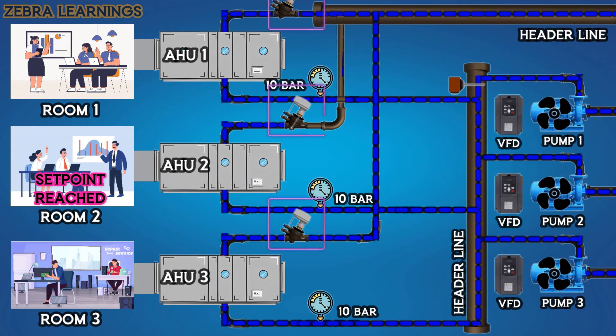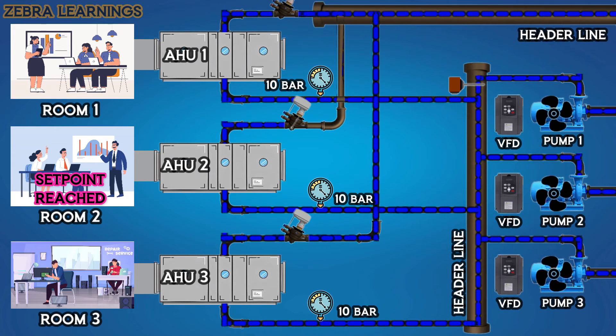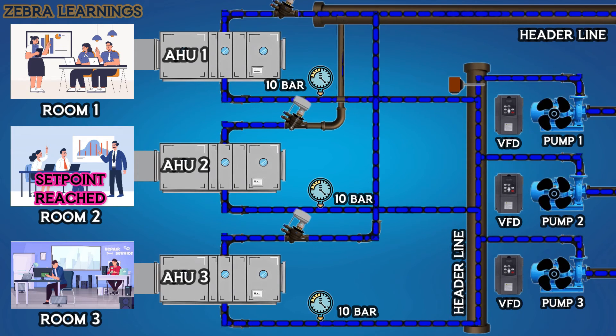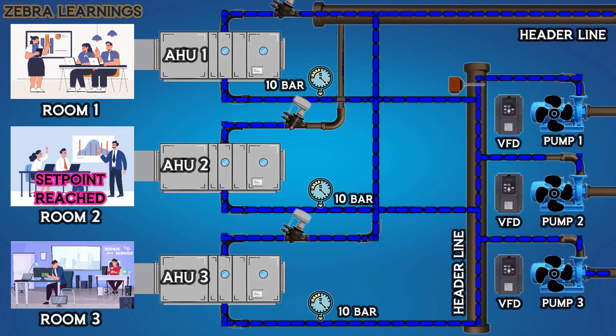If a 2-way valve is used in the AHU, a VFD is used in the pumps. Because when the 2-way valve opens and closes, the speed of the pump should be increased or decreased through the VFD. By this, a constant pressure can be maintained in the pipeline.